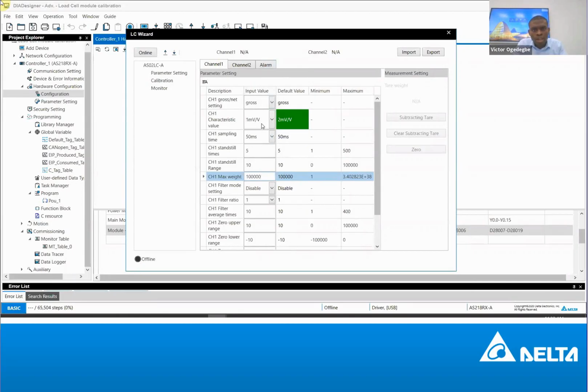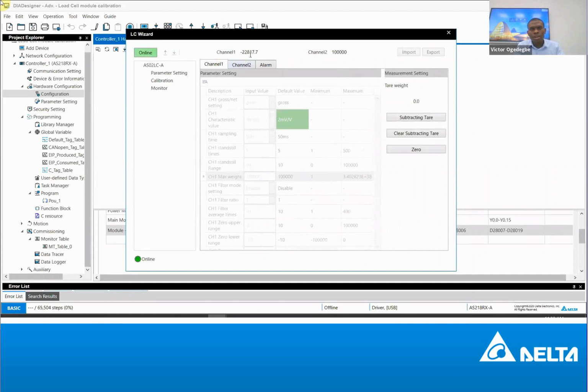So then let's continue. I'll select 1 as the gain value. We want to measure gross weight. So this is the first main configuration you have done. So let's download. You see download sources. I've downloaded to the module. Then let's go online. So you see I'm online. This is the value I'm seeing. This value is from the sensor.